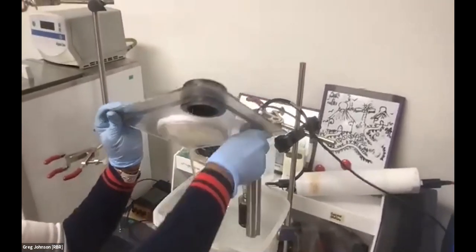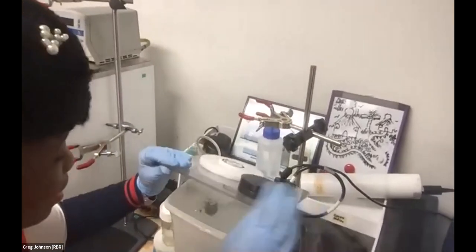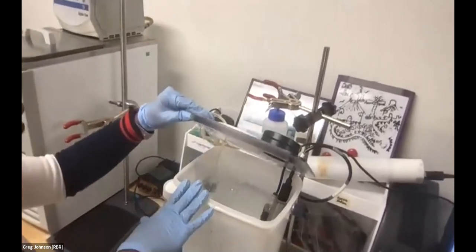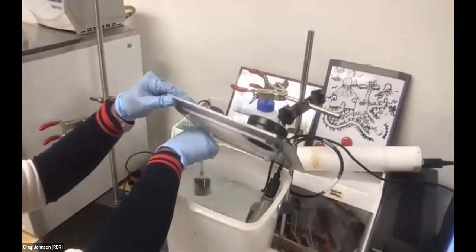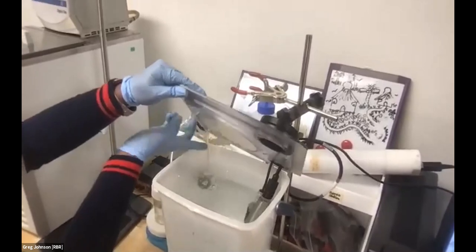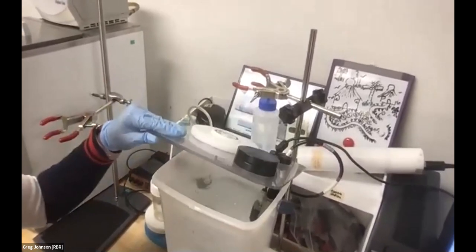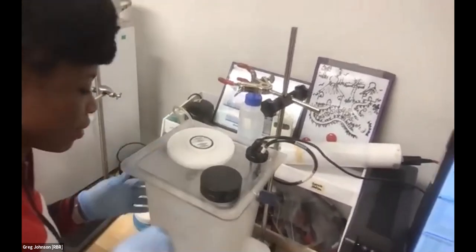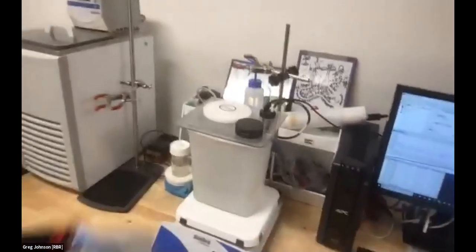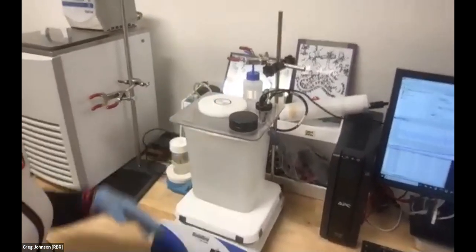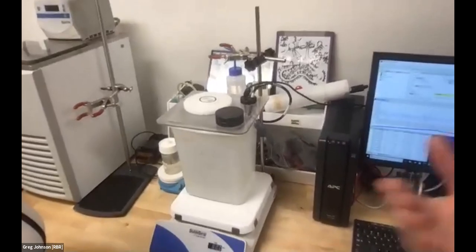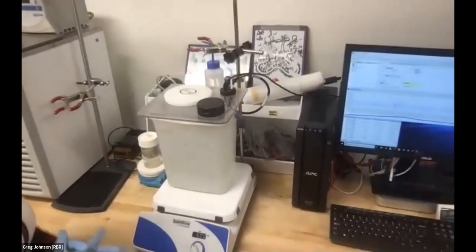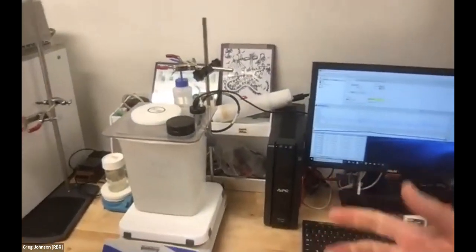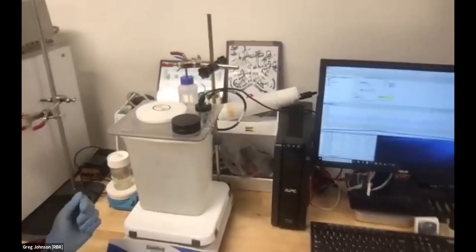that's just a resident, permanently stays in there. It's distilled water, so it's air saturated water that we use, and that's just a bubbler to get the water. Like from an aquarium, really? Yes, really. And there's a stirrer in there to keep things going. This is where we do our last checks before the instruments get shipped. So this isn't really the calibration, it's more the quality check. Yes, it is. And here we're just doing a quality check at 100% saturation.